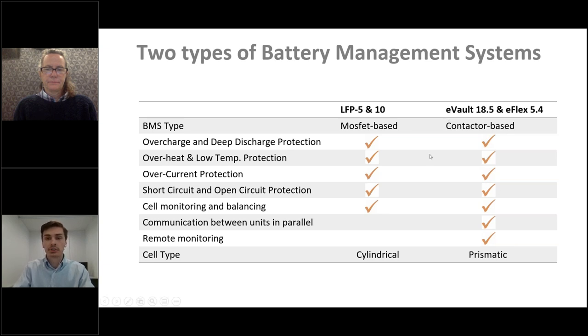So it has all the protections that a MOSFET-based BMS has, but it also has communication between units in parallel, and the remote monitoring features that will be rolled out in the next couple months or so. It's really about having the safety standard as well as the communication. This contactor-based BMS, in terms of the eFlex, allows closed-loop communication with those inverters I mentioned before. And like I said, the eVault is still testing, so if you need an immediate solution with closed-loop communication, the eFlex is certainly the way to go.